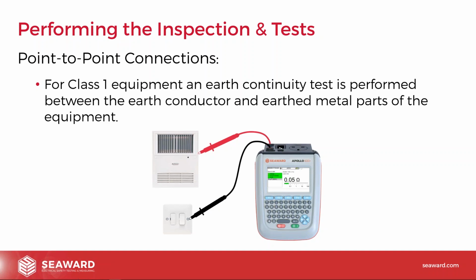You'd be surprised how often that's missed off, where people have installed something and there isn't an earth connection, but because nobody's checked the final bit of the circuit, they've checked up to the spur when they've done an R1, R2 test, but they've never checked it to the connected equipment, and sometimes things have not been earthed correctly, or the wrong part's been earthed, or the earth has become detached for some reason.